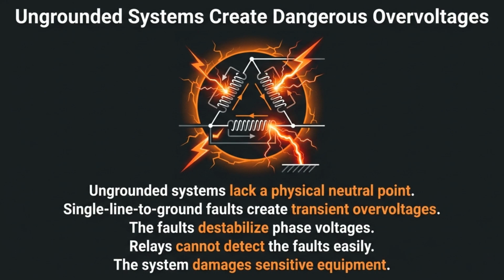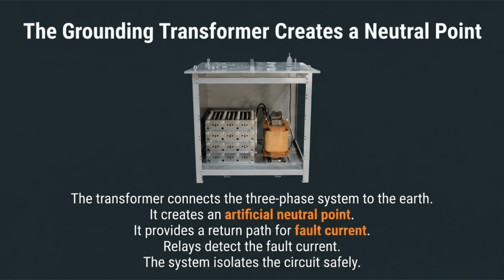Ungrounded systems lack a physical neutral. This deficiency can lead to dangerous transient overvoltages during single line-to-ground faults, which destabilizes phase voltages and poses a serious risk to sensitive equipment. A grounding transformer solves this by connecting the three-phase system to the earth, creating an artificial neutral point. This provides a return path for fault current, allowing protective relays to detect and safely isolate the circuit.